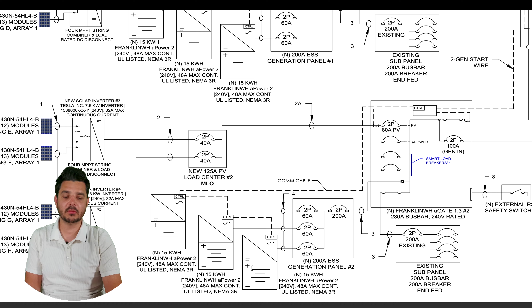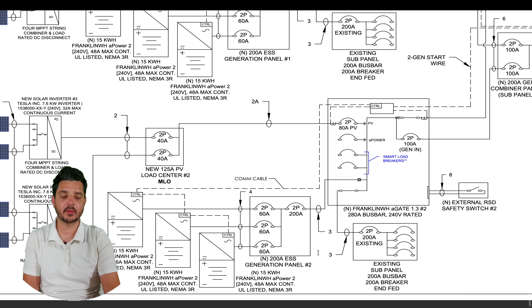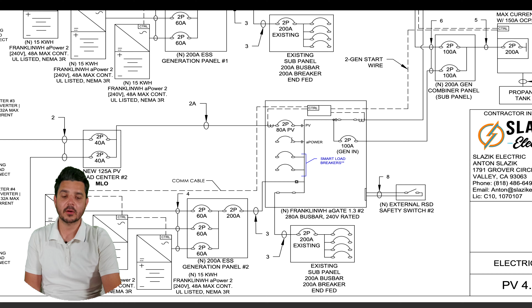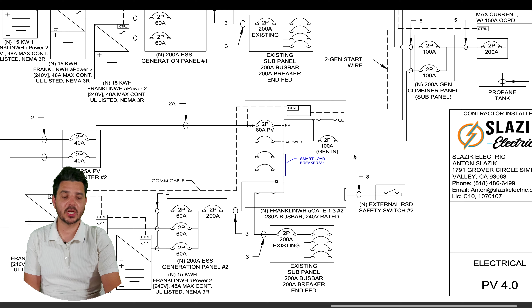We got 6 aPower units for the other 200 amps that we're backing up, and those are being combined in a 200 amp sub panel. And then again, we're using the extended backup lugs kit, not the Franklin aPower circuit breaker slot, and then we have the generator feeding into it as well, and we have that external rapid shutdown safety device.